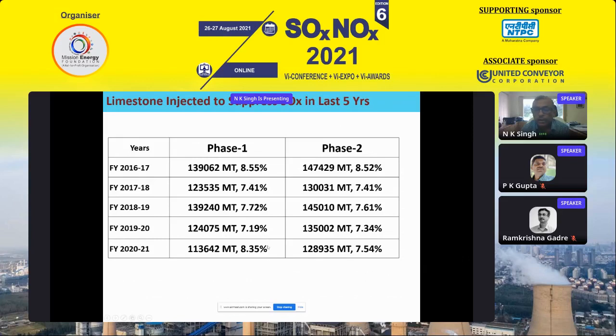This is in percentage. If you see, it varies, though it is designed for 10%, it is 7 to 8%. Our lignite feed is almost 100 to 140 ton. So we are feeding limestone at around 7 to 8%. That depends upon the emission level and the quality of the limestone. But we have our own captive limestone mines, and from that we are feeding this. So it is a range. What I mean to highlight is that this is low-grade stone, but it is being used and it is fully meeting our requirements.